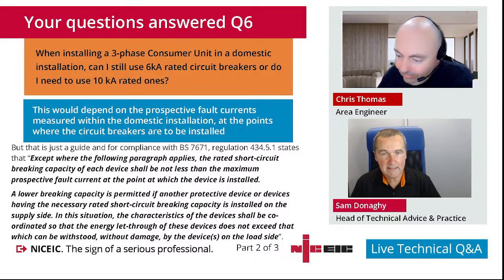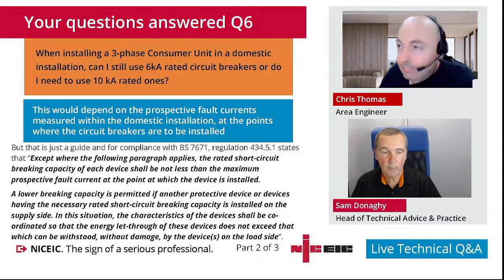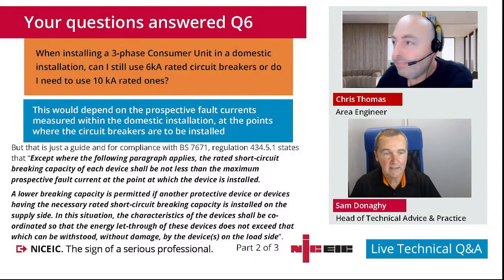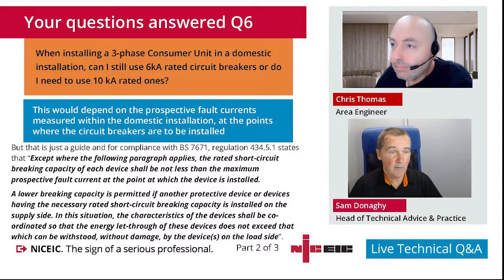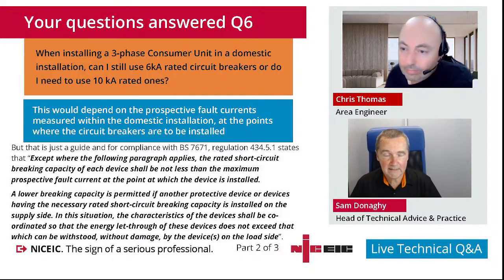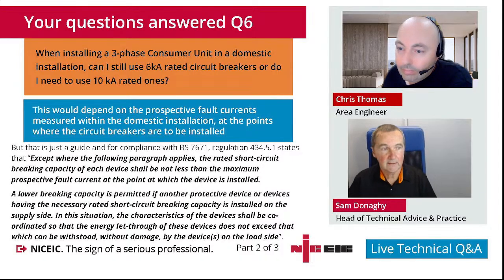So yeah, there's nothing that says you can't put a 6 kA device in a three-phase board, just in the same way as there's nothing that says you can't put a 16 kA in a single-phase board. But the breaking capacity of the protective device has to reflect the prospective fault current, short circuit and earth fault that circuit is going to experience at the point where the protective device is.